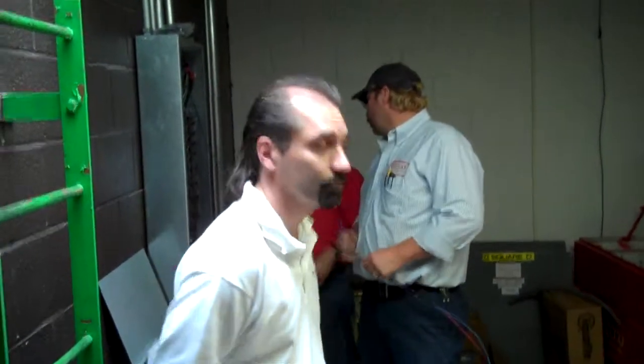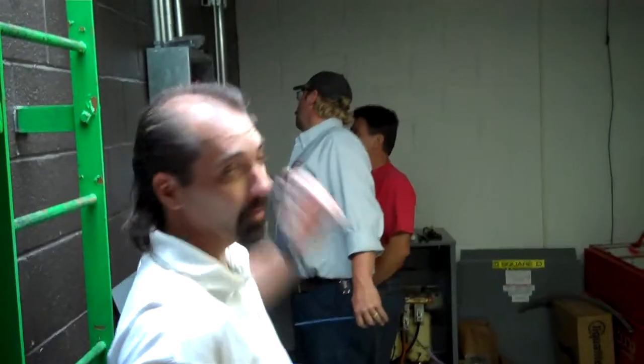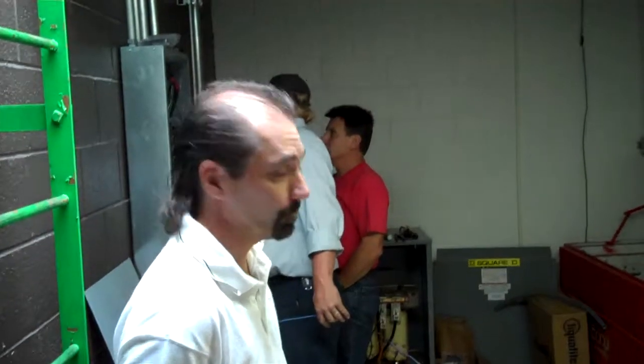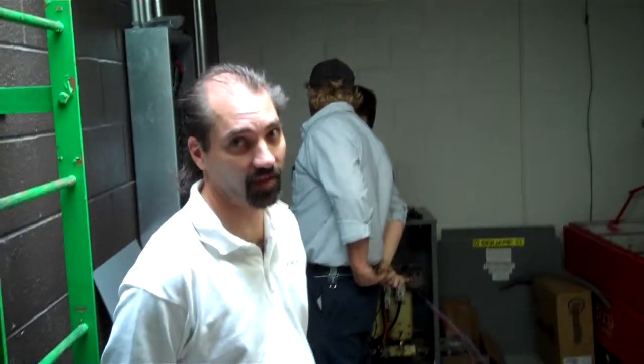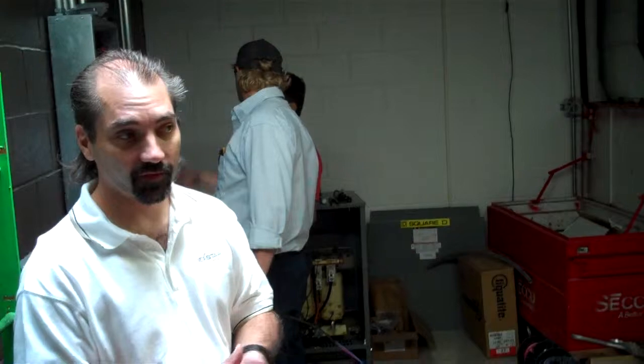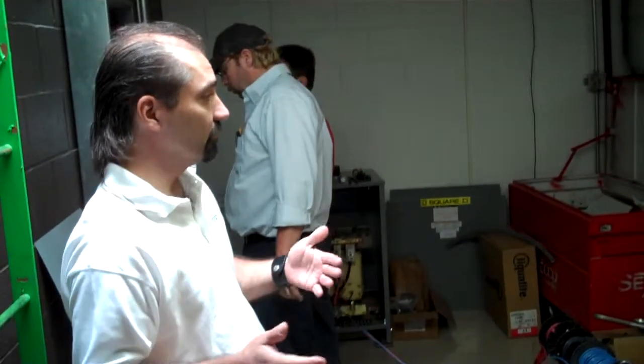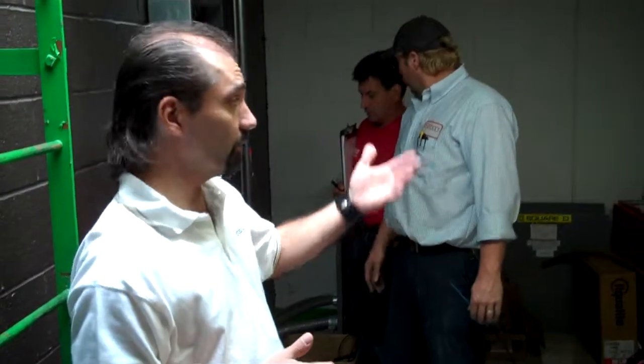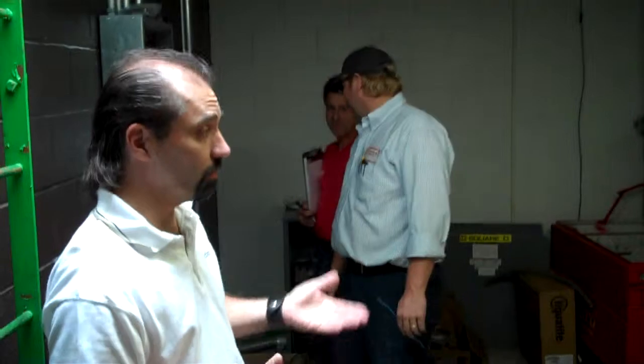So that's a pretty innovative way to do a school building like this without having to install ductwork everywhere, and being able to provide fresh air, which is important to a classroom, and get rid of the carbon dioxide and a lot of the moisture, and not just exhaust the air, losing all that heat. You're able to recover it and save the school a lot of money. Essentially, let's just say, for example, we had 40 tons of capacity in this building. Typically, to meet outside air and exhaust requirements, you may exhaust up to 30-40% of that capacity and waste it, where we're able to recover that and recoup it back into the space, where we're only essentially wasting up to 15%. So that's pretty huge.